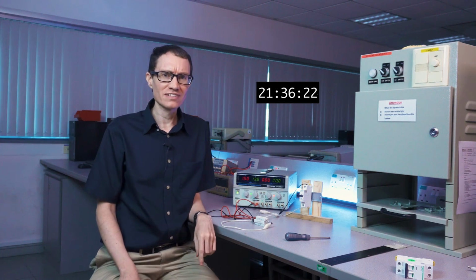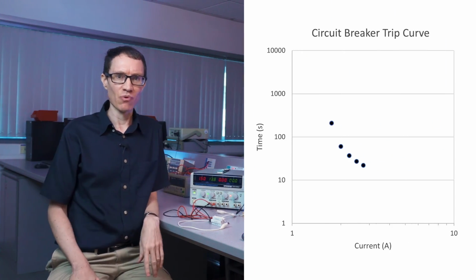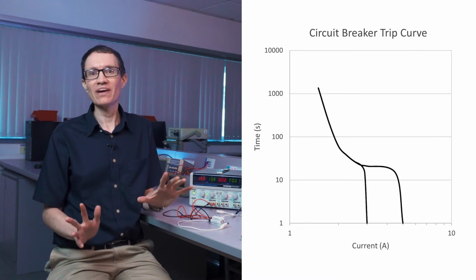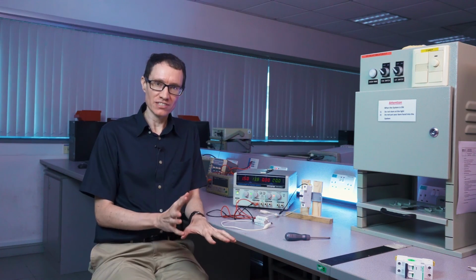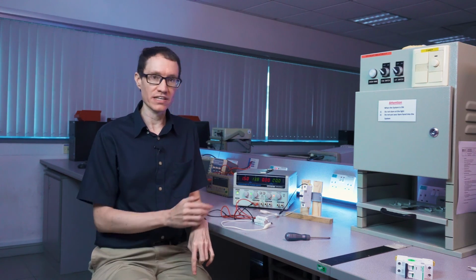Well, it's already been quite a long time here, and I'm getting tired of waiting for this circuit breaker to trip. I think we have the idea here. A common misconception about circuit breakers is that they'll trip when you have more current flowing than what's printed on the circuit breaker, but obviously that's not true. It takes these things quite a long time to trip.